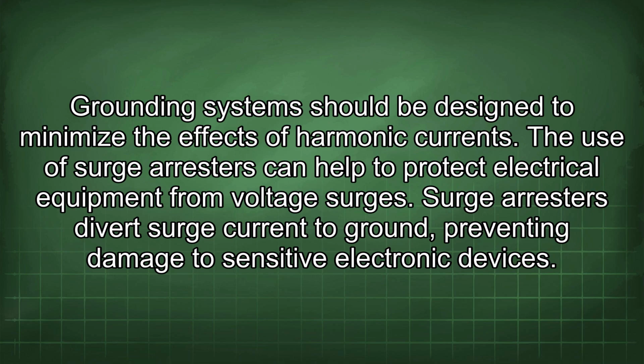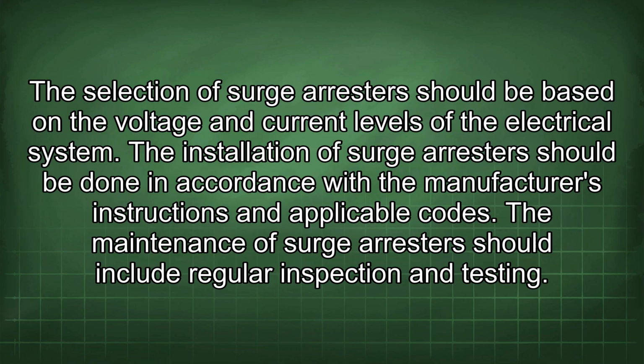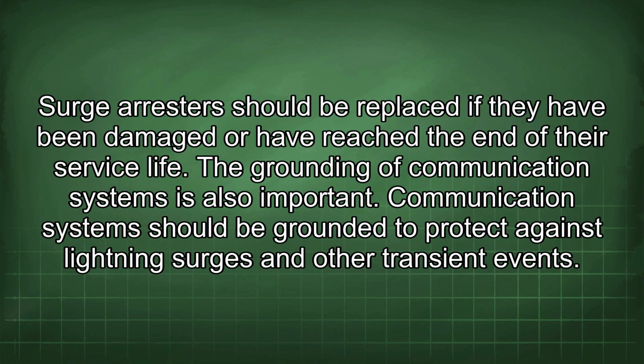The use of surge arresters can help to protect electrical equipment from voltage surges. Surge arresters divert surge current to ground, preventing damage to sensitive electronic devices. The selection of surge arresters should be based on the voltage and current levels of the electrical system. The installation of surge arresters should be done in accordance with the manufacturer's instructions and applicable codes. The maintenance of surge arresters should include regular inspection and testing. Surge arresters should be replaced if they have been damaged or have reached the end of their service life.